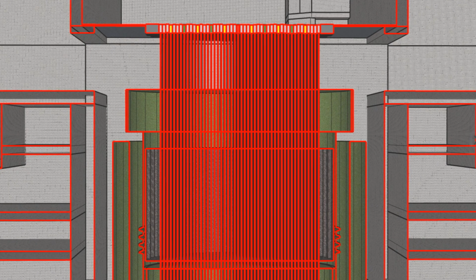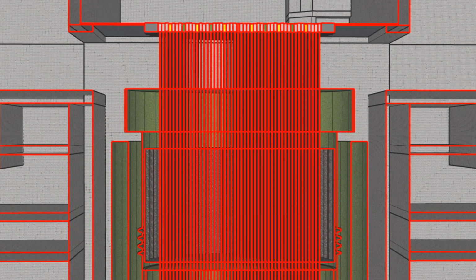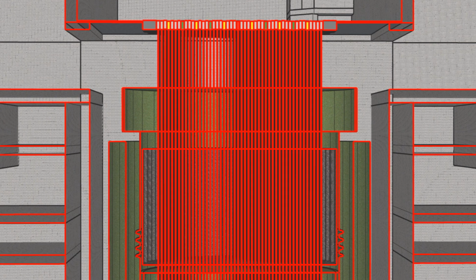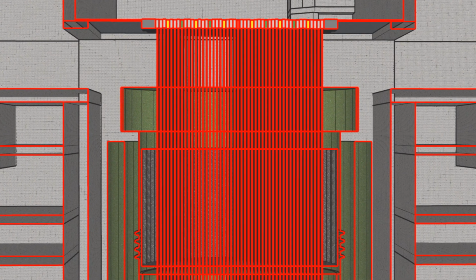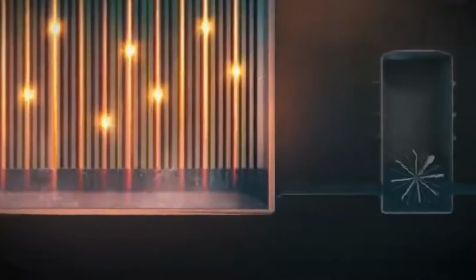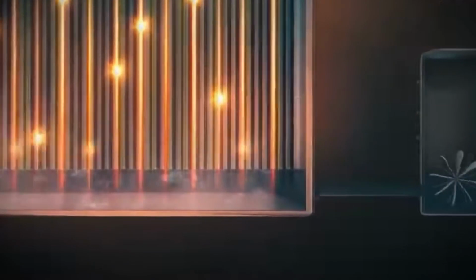Operators were confident that the Level 5 emergency protection button EPS 5 would shut down the reactor in any situation. But it turned out that under certain conditions, the emergency protection system could cause uncontrolled power increase. The IAEA Commission found that at power levels below 50%, the control instruments did not provide full feedback. The danger of working at low power and with a small reactivity margin was not well described in the operating documentation. Operators could not see some important parameters and often had to rely on their own experience and intuition.